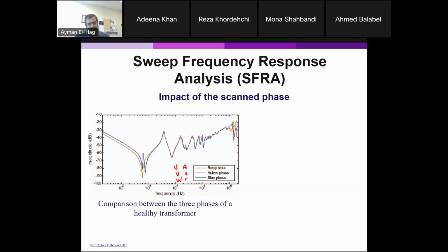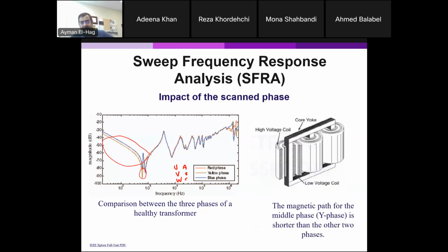So for the middle phase here, you see, in the core area, this is all low frequency. Low frequency means in the core area there is a discrepancy. Why is that? It's very simple. If you look at the structure of the transformer, this is the middle phase, phase yellow or phase V or phase B. When you energize the transformer, this is the core path. The flux will go here and will go there. Now for the other two phases, the core seen by the winding is different. For the right or the left, this is one path of the flux, and this is the other path.